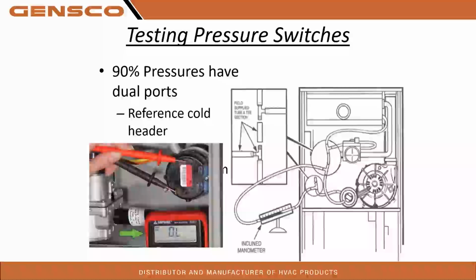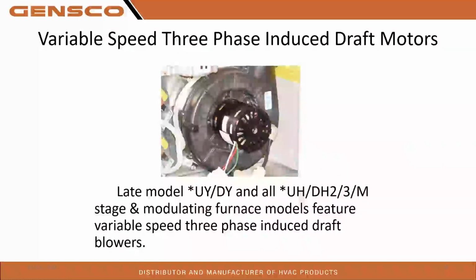So 90% furnaces have dual ports. We've got to reference the cold header or the intake air going into that burner. So we're going to tee in, we're going to get a manometer and reference the burner to be able to get true readings. So we're teeing into the pressure switch and into the reference to the burner there. So you're going to have some tees with you. If not, Lowe's has got them for pretty cheap. Get you a couple. Okay.